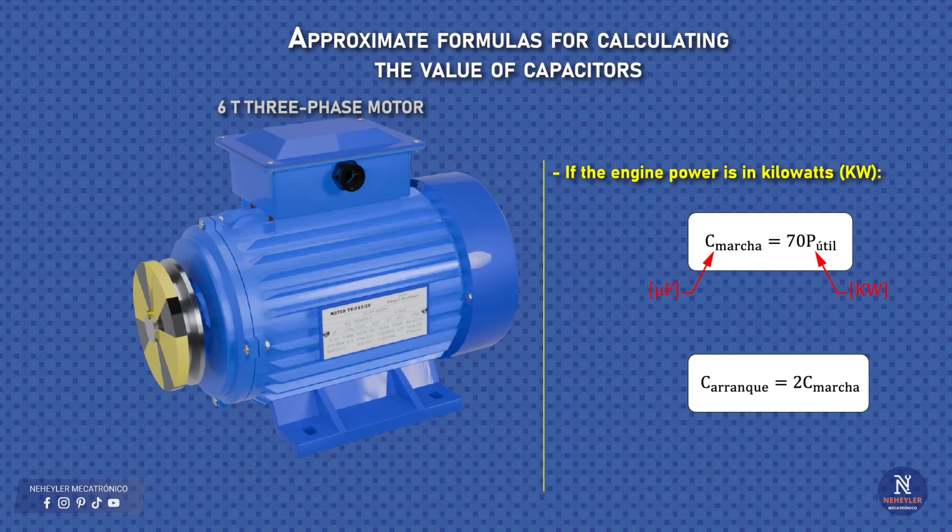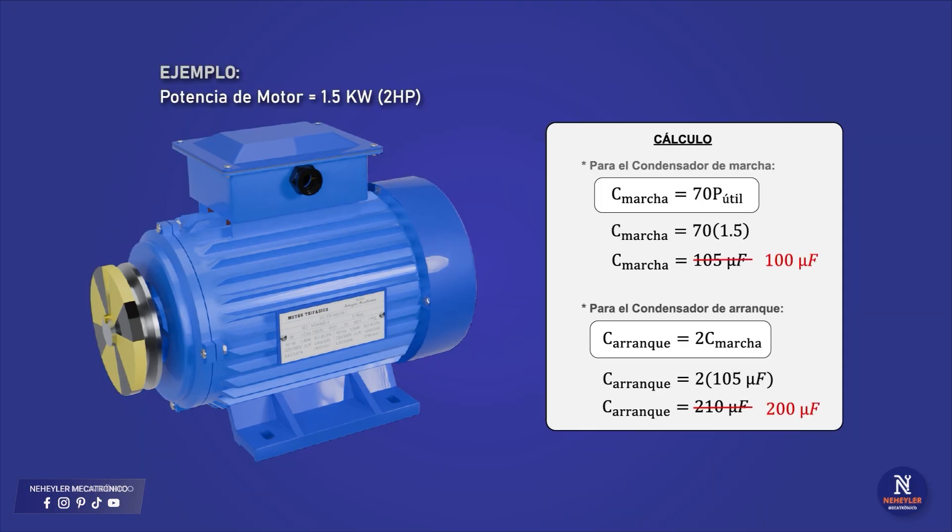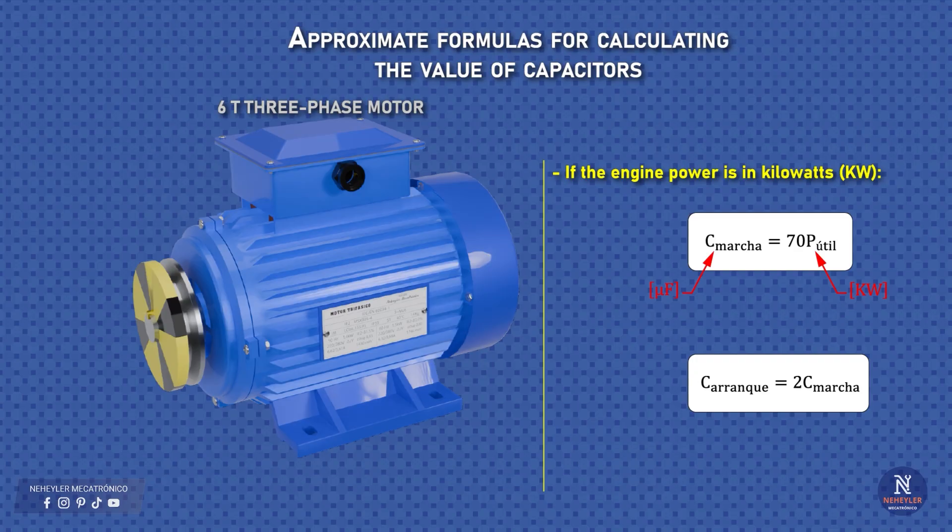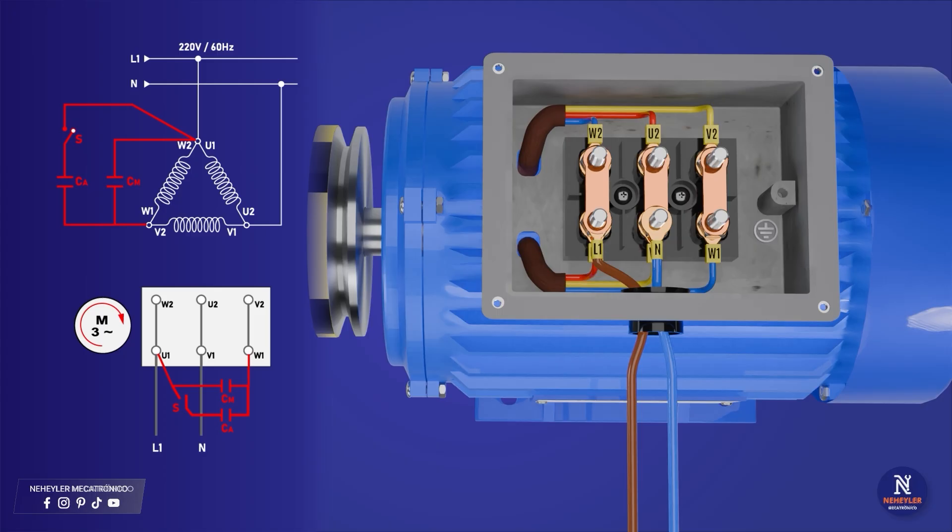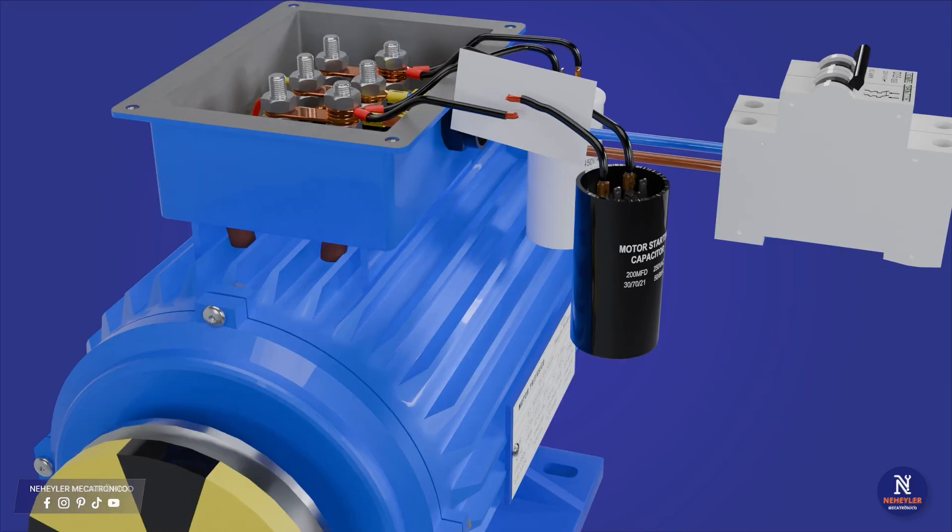The calculation of the capacitors can be done in a very practical way. For the run capacitor, an approximate value of 70 microfarads per kilowatt of motor power is used. And for the start capacitor, simply use double the run capacitor. This calculation was already explained in detail in the previous video, so here I only mention it as a quick review. The main topic of this video is the manual and automatic disconnection of the start capacitor in a three-phase motor powered with single phase.